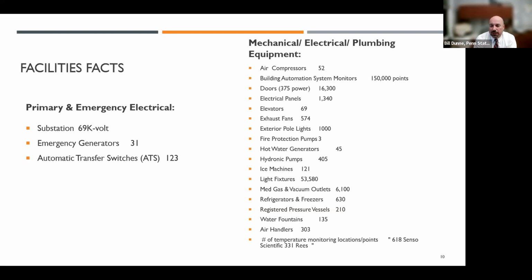Then humidity, especially in operating rooms or other interventional areas with high volumes of medical gases, including flammable gases or oxygen, which causes fires to spread more rapidly. We maintain humidity a little higher in many cases so we don't increase flammability, but we also don't want too much humidity, which causes components of infectious disease issues, like mold buildup, or very high humidity or dewy environments. We want to monitor those things 24/7.